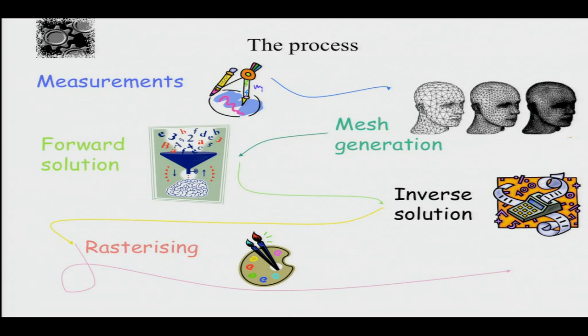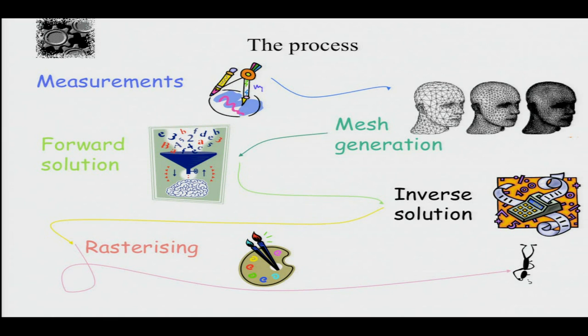To summarize the process: make the measurements, generate a mesh specific to the clinical application, solve the forward problem, solve the inverse, rasterize it, and give it to a clinician to interpret. It may not mean structure; it may mean change. For example, the images shown earlier were of volumetric change — that color indicated the total volume of the lung changing in time, not necessarily the shape of the lung. Respiratory clinicians need to know how the lungs are expanding, which is quite important because we still don't have a real-time method of looking at all lung inflation. The left lung might compensate for the right lung, or the bottom might work harder. This is a niche area where EIT can contribute.